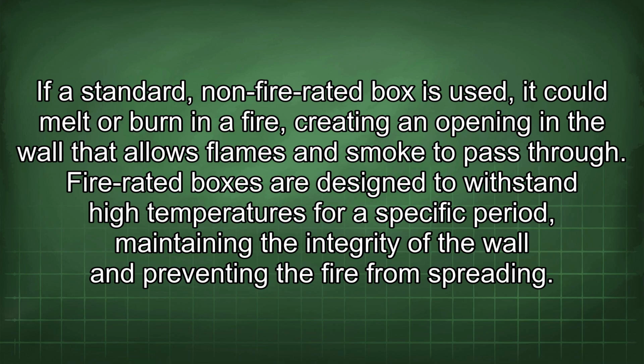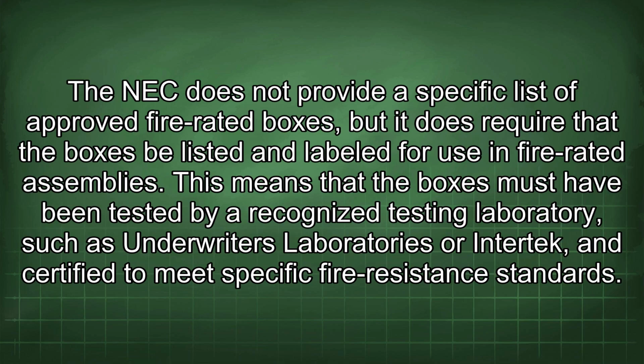Fire-rated boxes are designed to withstand high temperatures for a specific period, maintaining the integrity of the wall and preventing the fire from spreading. The NEC does not provide a specific list of approved fire-rated boxes, but it does require that the boxes be listed and labeled for use in fire-rated assemblies. This means that the boxes must have been tested by a recognized testing laboratory, such as Underwriters Laboratories or Intertek, and certified to meet specific fire resistance standards.